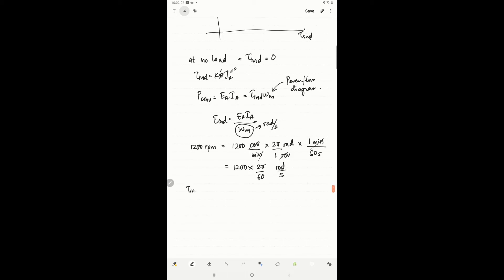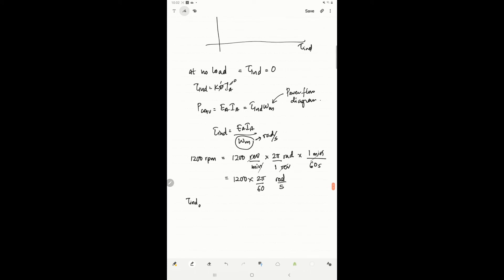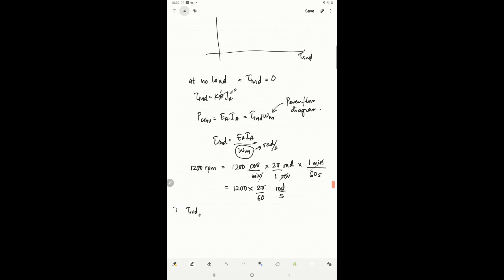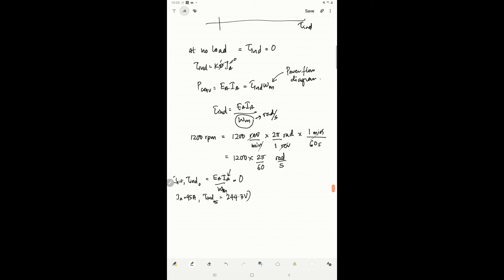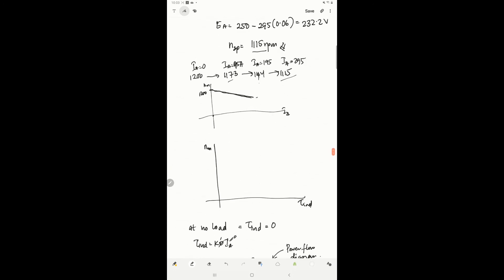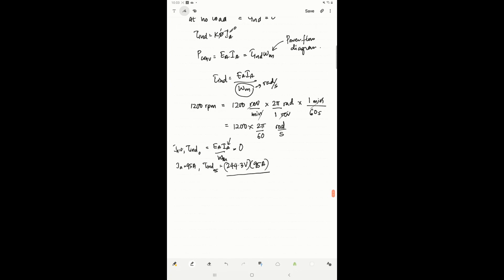For each speed, we calculate the induced torque. When ia equals zero, induced torque equals ea·ia over omega_m, and since ia is zero, torque induced is zero. When ia is 95 ampere, torque induced equals 244.3 volts times 95 ampere divided by 1173 times 2π over 60 radians per second, which gives 190 newton-meters.